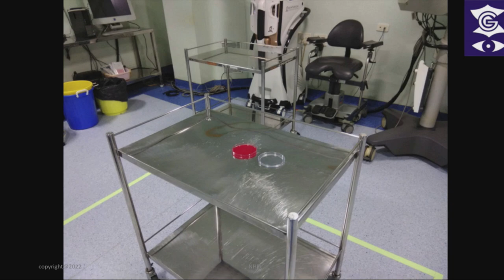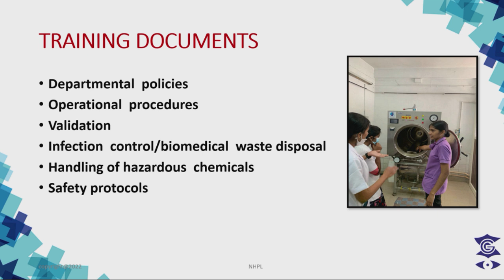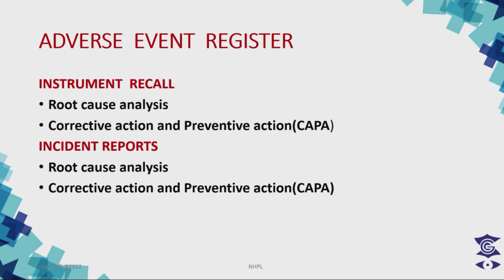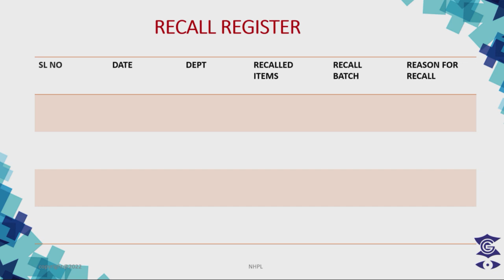And coming to the training documents, this has the departmental policies based on which we can train the OT staff and the nurses: the operational procedures, validation, infection control and biomedical waste disposal, handling of hazardous chemicals, and safety protocols. Based on all this, the OT staff and the nurses have to be thoroughly trained. And we also maintain an adverse event register and an instrument recall. So whenever there is an infection or when we are doing the root cause analysis, we can have an instrument recall based on the RCA done, corrective action and preventive action. Also, an incident report can be maintained for events which happen in the OT. This also has the RCA and the preventive action. This is how the recall register that we maintain looks.